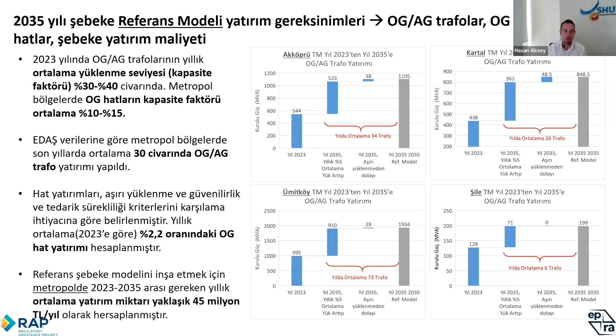We decided that nearly 30 low voltage and medium voltage transformers are required, and 2.2% investment is required for the medium voltage lines. So that was the purpose, to create the reference model in order to meet the energy load.